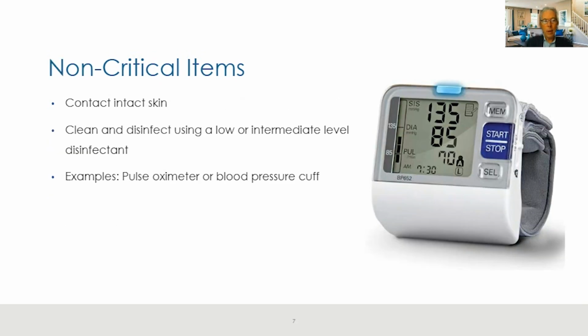Non-critical items, that's a little bit easier. We're talking about things like pulse oximeters and blood pressure cuffs. These typically contact only intact skin, so there you could clean and disinfect with a low or an intermediate level disinfectant.